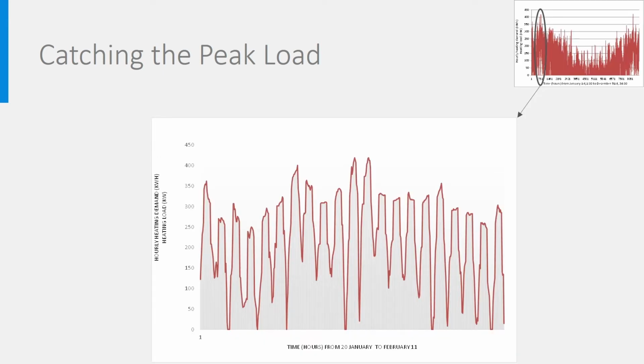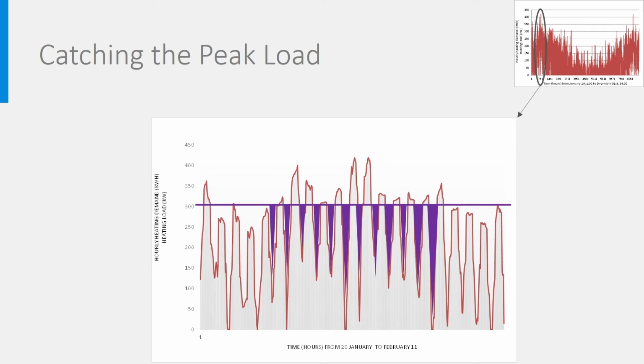The previous slide may be a bit abstract, so you see it now for a part of the hourly profile on which the load curve is based. If I size my heater to 300 kW, just like we did, you can see here where the possibilities are to charge the buffer. In this office building, that would be at night, when little heating is normally done, because there is nobody in the building. You could do exactly the same for cooling.